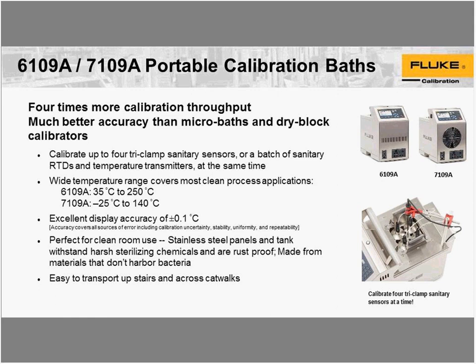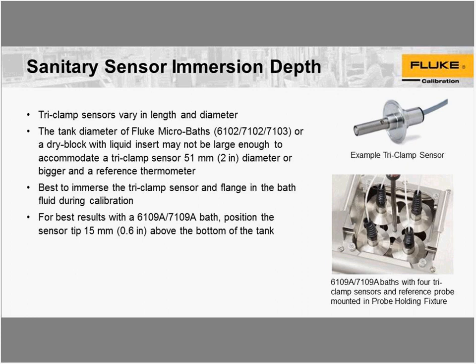And there are also handles on the sides on the bottom between the front and rear feet, so that if you have this on a bench, you can reach underneath on each side, and there are handles up under the frame to make it. You can move it on a bench or on a cart if you can't lift the handle. They are fairly heavy, so the handles are strong for that. Already talked about the sensors vary a lot in length and diameter, and can be a very big challenge for someone to calibrate.